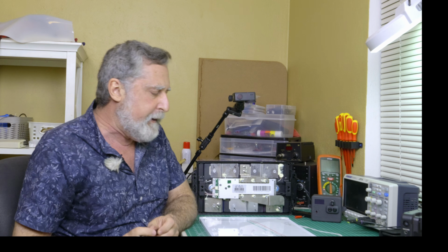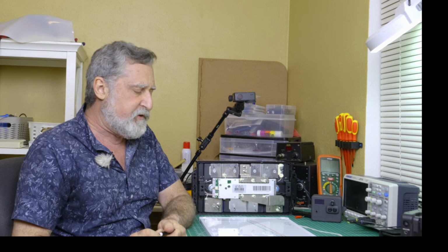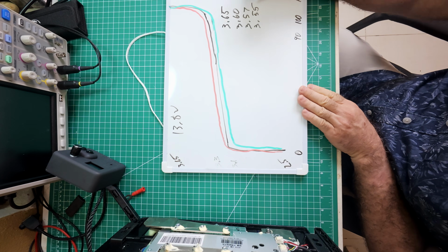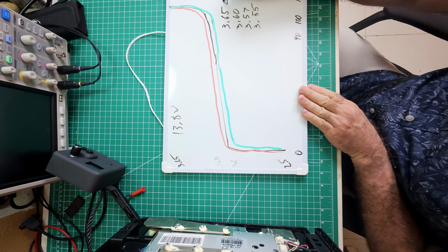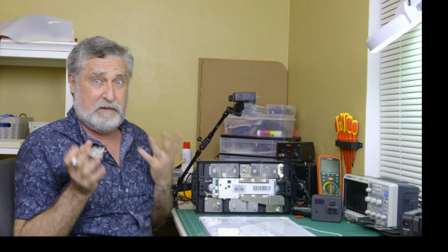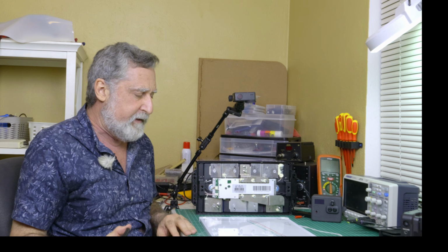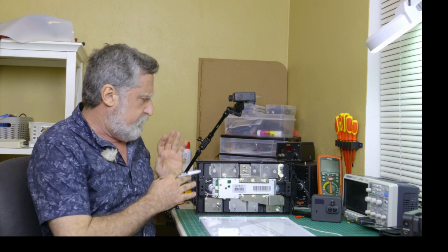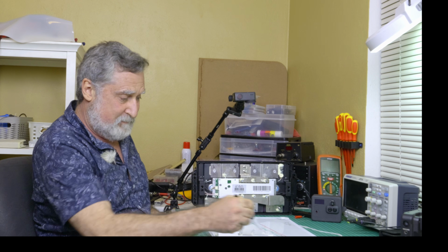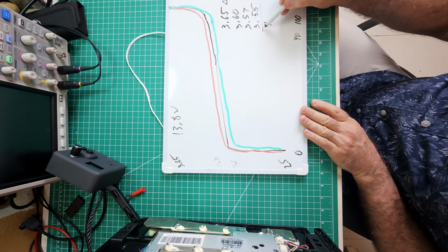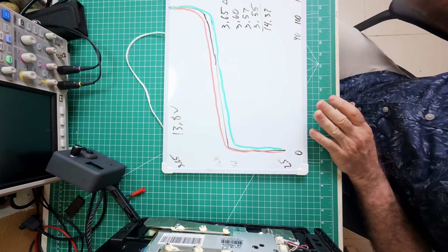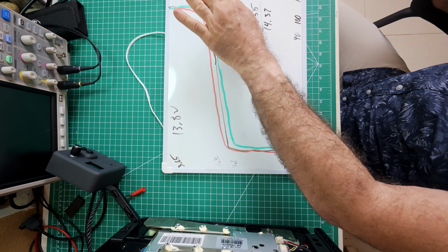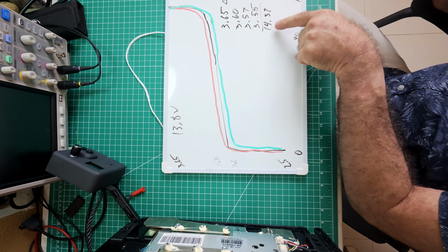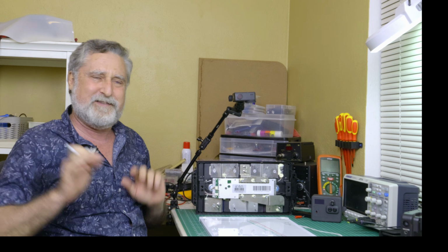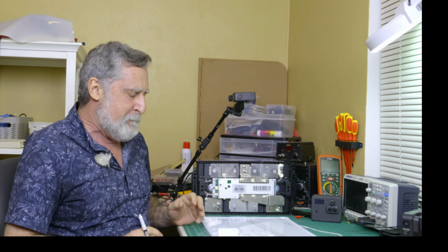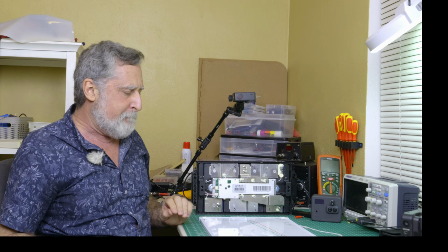If that was my battery, I would stop attempting to charge it anymore. The delta now between the lowest cell and the highest cell is 0.1 volts. I just arbitrarily decided that was okay from some experience. If I watch the total voltage, just adding all those together, we get the battery shutting down at 14.37 volts. If they were all perfectly balanced and all shut down at 3.65, that would be 14.6, which is kind of that magic number. That's the limit to where you should charge. But that battery is in pretty good shape.